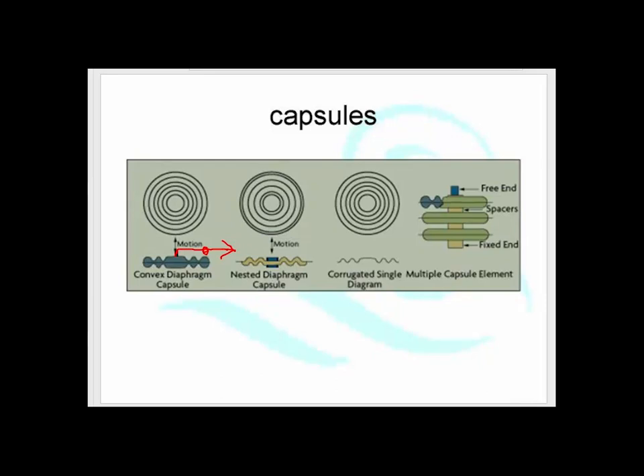All of these machines, the Bourdon tube and the capsule, are both mechanical, and they have a tendency to stick. So if you want an accurate reading off them, you have to go up and give them a little tap, and they'll move to their correct position. But they all have a slight tendency to stick, and if you're ever calibrating one of these, bear that in mind. You might need to give it a little tap, because it's always funny when somebody's calibrated a Bourdon tube, and I go up to it and say give me 2,500 kPa, and they do it, and then I tap it, and the needle moves by 5 millimeters. So that's something to bear in mind.